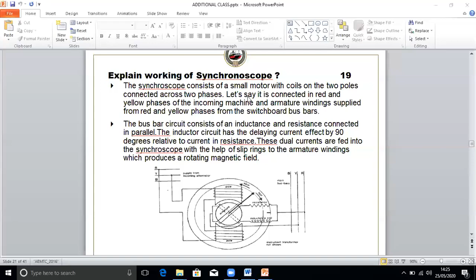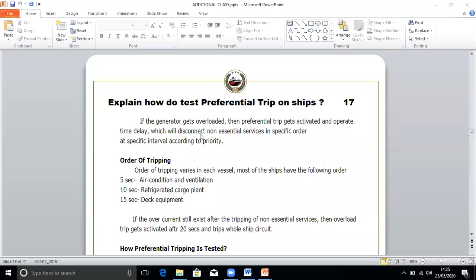Okay, sir, I have one question on this preferential trip. You said we will check the preferential trip by injecting current. How do we do this? We don't inject it. When you're testing it on board ship, there is some testing method. Otherwise, you have to increase the load. You have to take the standby generators off load, and you actually have to increase the load.